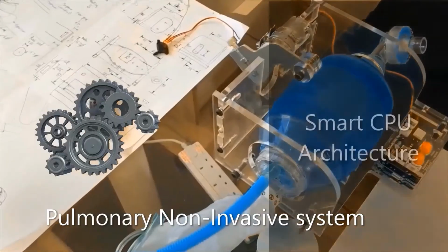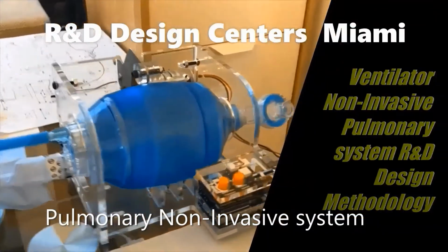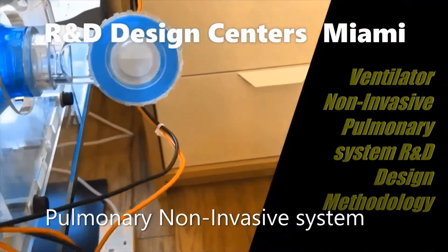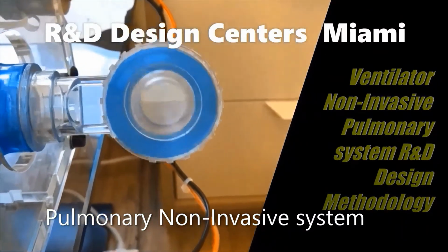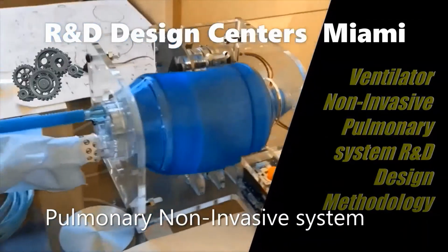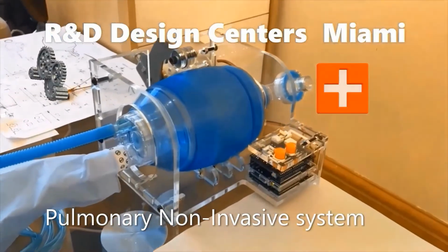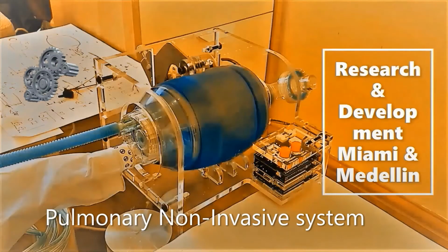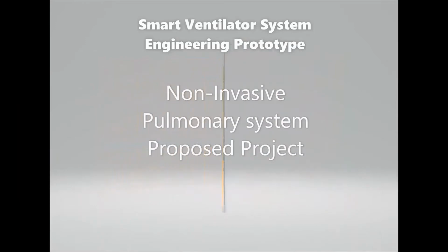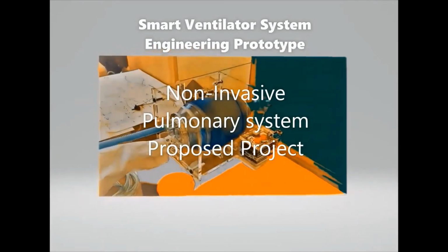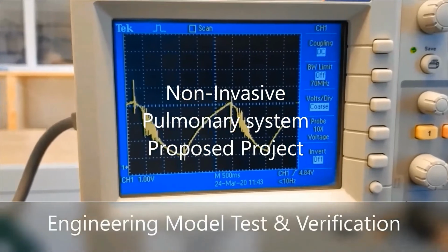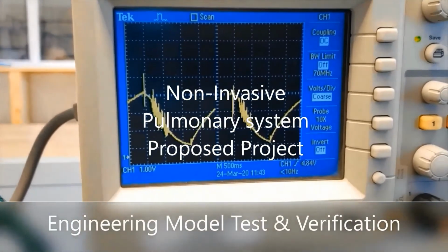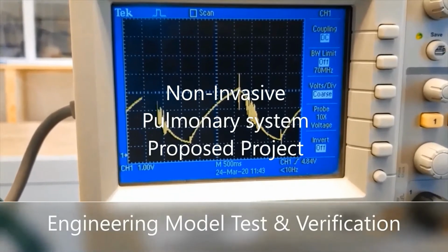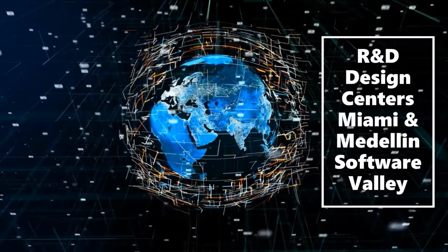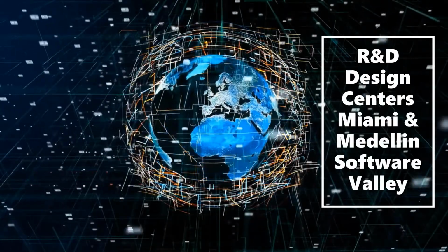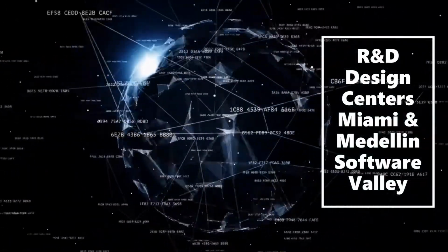The time-based frequency of the system ranges from 5 to 30 breaths per minute. This is the mandatory breath. At this point, the patient must be heavily sedated. The machine needs to trigger the breath cycles and end the breath cycle as well. The embedded CPU will detect and control the breath trigger and timing. There are a multitude of other design parameters and considerations that need to be taken into perspective.